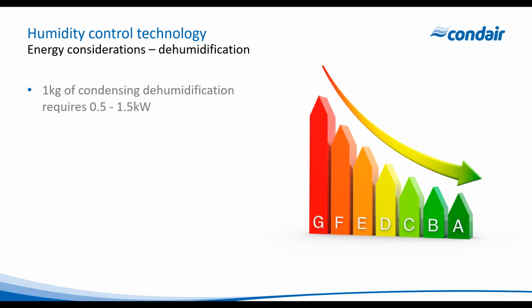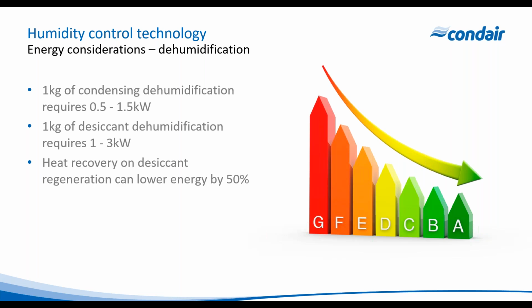So, energy considerations for dehumidifiers. Well, 1 kilogram of condensing dehumidification will typically require 0.5 to 1.5 kilowatts. And 1 kilogram of desiccant dehumidification, typically 1 to 3 kilowatts, again, depending on what power we're using for that regeneration. And we can utilize heat recovery on desiccant units, where we take the regeneration air and pass that through a heat exchanger to preheat the regeneration air. So system design and selection and consideration for energy is a critical factor.